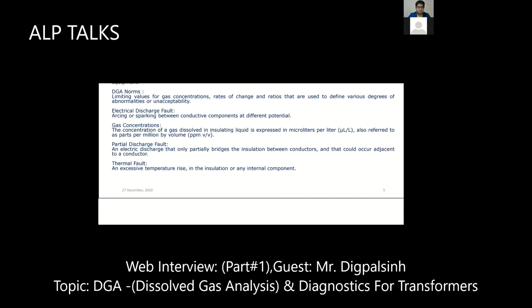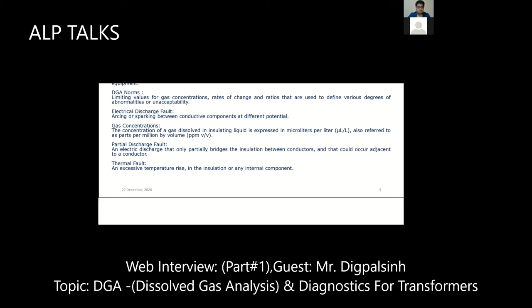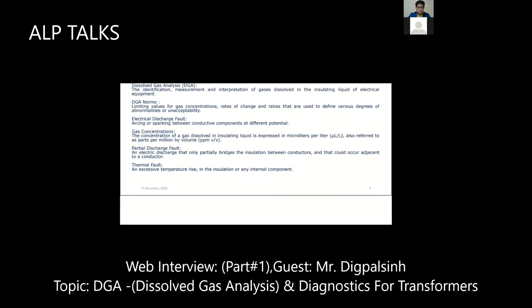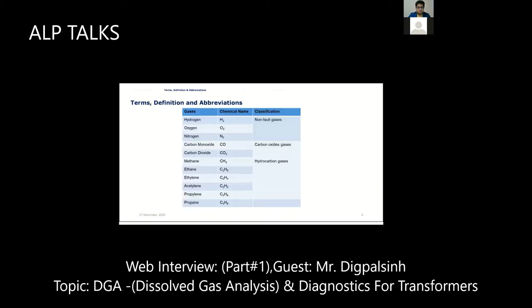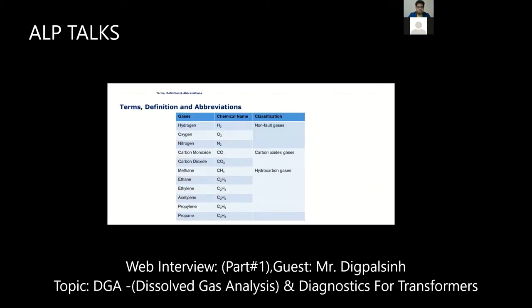Then gas concentration. When we measure gases in a power transformer or any other electrical equipment, it is expressed in microliters per liter, and you can also say ppm, parts per million by volume. Then partial discharge and thermal fault, everyone knows, no need to explain. Then these are some abbreviations, or you can say gases that we can find in a transformer.